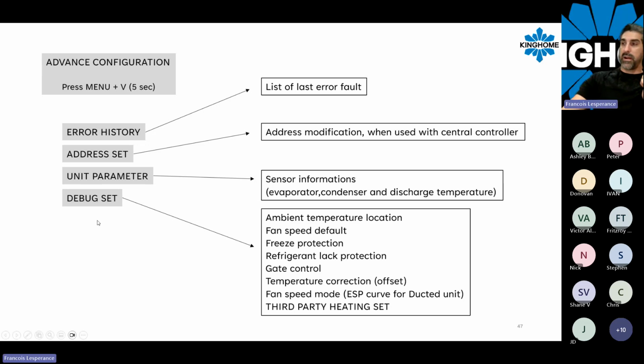The last part is the debug set. This is where you can change the ambient temperature location. For example, if you want to use the thermostat as the remote sensor, or you still want to use the return air sensor. This is mostly when you have a ducted unit, for example. You can set up your fan speed and a couple of other features inside this debug set also. A temperature correction: for example, if the room temperature is 21 and this controller is sensing 22, you can do a small offset of this sensor.